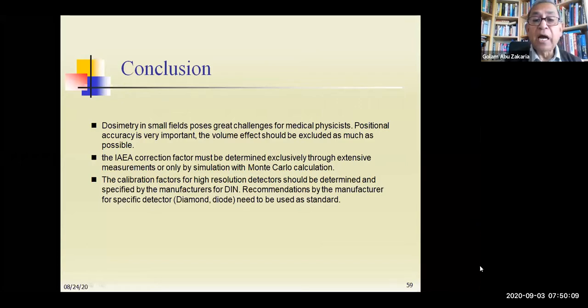The calibration factor for high resolution detectors should be determined and specified by the manufacturer for DIN. Recommendation by the manufacturer for a specific detector, a diode, needs to be used as standard, because in the DIN protocol, they do not give any calibration factor for any chamber for small field dosimetry. So you should determine it in the hospital, and then it needs very exact determination. So sometimes in the hospital, we have less time. So it is advisable that the manufacturer should give us a correct calibration factor like for the large chamber.